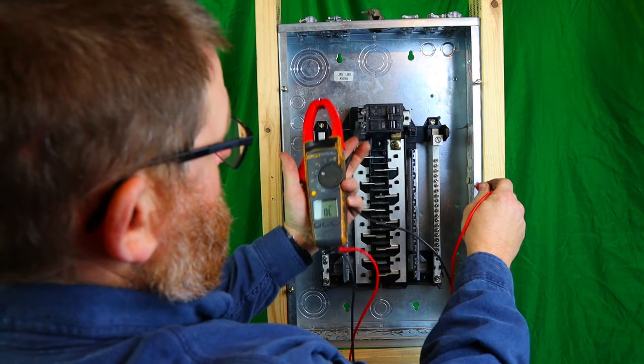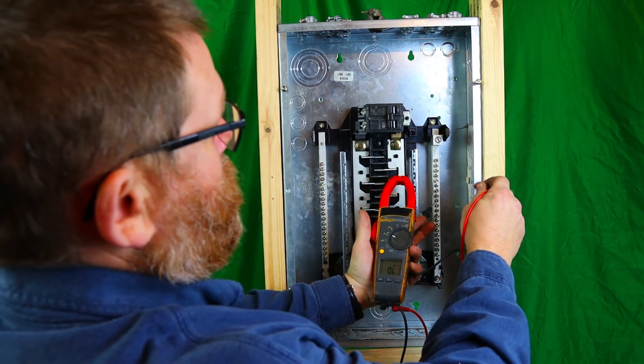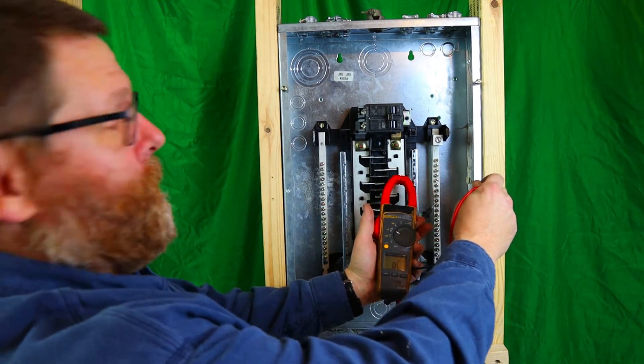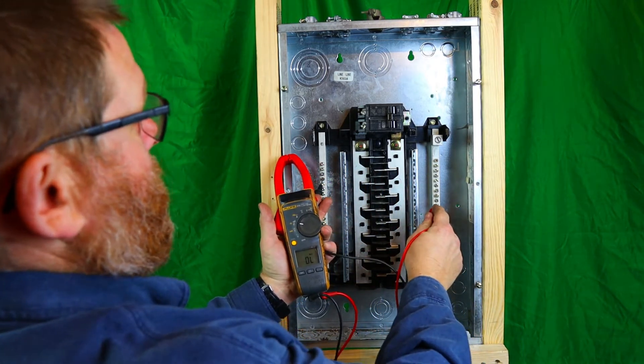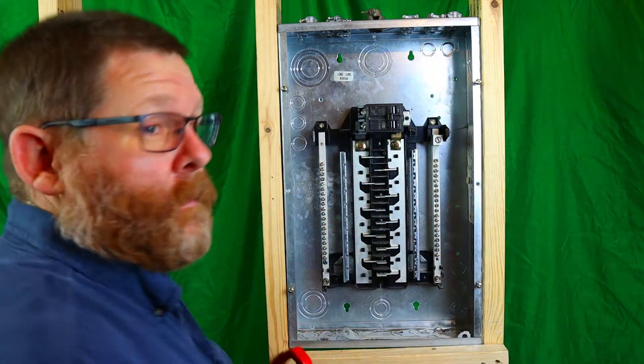And we're going to go to this neutral, and you hear nothing because that's the way it's supposed to be. If you go between them, nothing. But if you go back to the can... that is the way you separate them - only bonded at one spot.